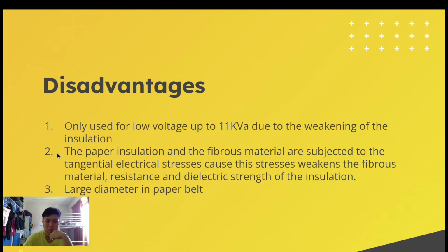The second one is that the paper insulation and the fibrous material are subjected to tangential electrical stress. This stress will weaken the fibrous material resistance and the dielectric strength of the insulation. The third one is that the cable has a large diameter because of the paper belt, and this will cause the size of the belted cable to become bigger and bigger. That's all for me.